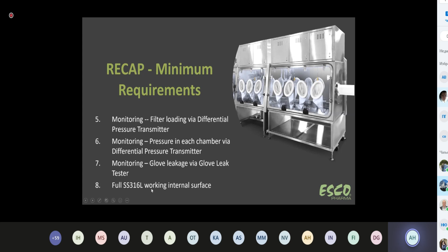Did you know that the PIC/S guidelines for good practice to prepare medicinal products say you should monitor the pressure across each filter before you start work? You should check every glove for leakages. At the minimum, you must do a visual check by eye. But ESCO doesn't like to check visually. We want to check using a proper glove leak tester. We also have to perform a pressure hold test before the start of each process. And a reminder: monitoring of the isolator performance is critical. We must regularly check the integrity of the isolator and gloves, and we should have preventive maintenance at least once a year.